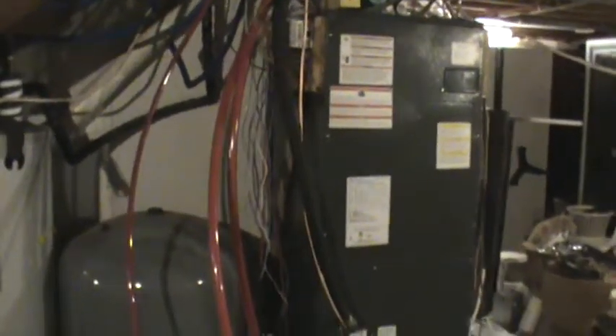And then this PLC actually makes the decision of whether to pull heat from the boiler or turn on the heat pump. And it depends on the temperature outdoors, depends on how much heat the system is calling for, because that heat pump can be in a high or a low mode. It depends on whether the boiler is ready. Does the boiler have hot water in it that can warm the home, or do the tanks that I've got have hot water in them that can warm the home?